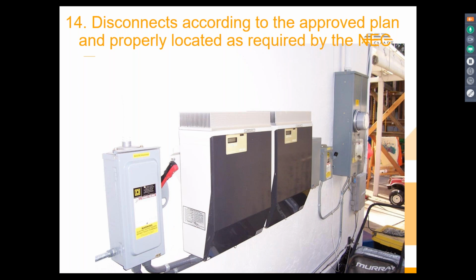Correct. So this is a case of a load side connection. So it's going into a circuit breaker. But you're correct. If this is on the supply side of the connection, if it happens to be going in and picking up the supply side of the conductor between the main disconnect and the meter, then this would be a fuse disconnect. And that would be the right location for it. And it could also be the visible break switch for the utility. They could get both out of it.